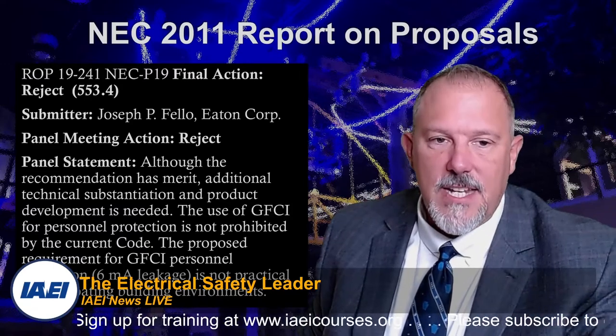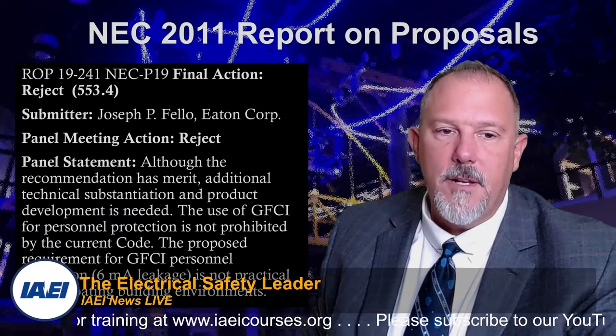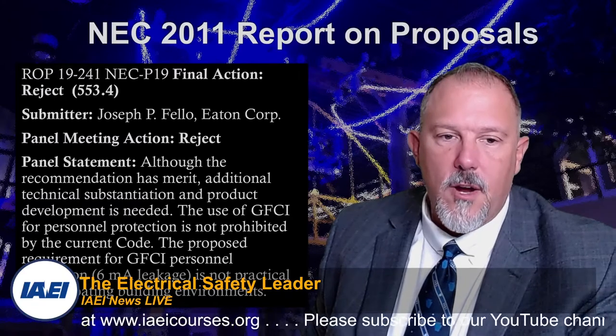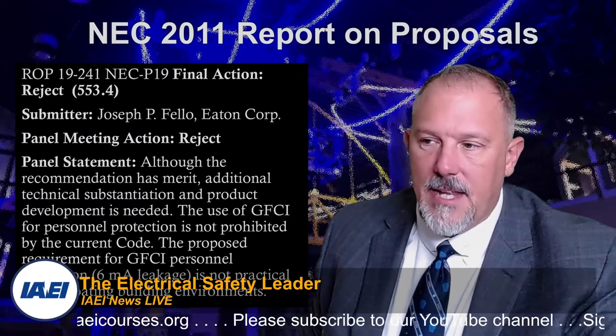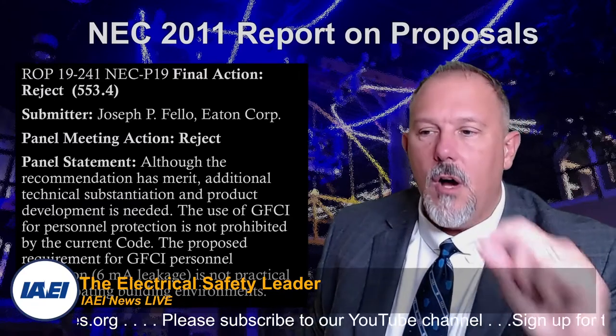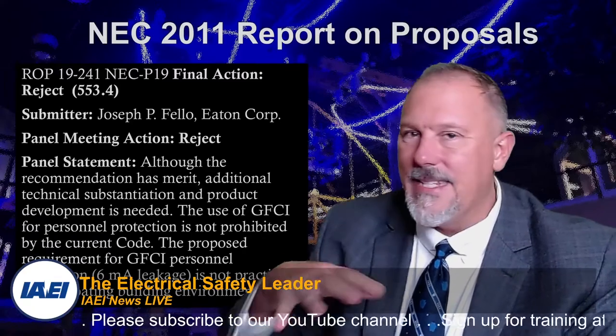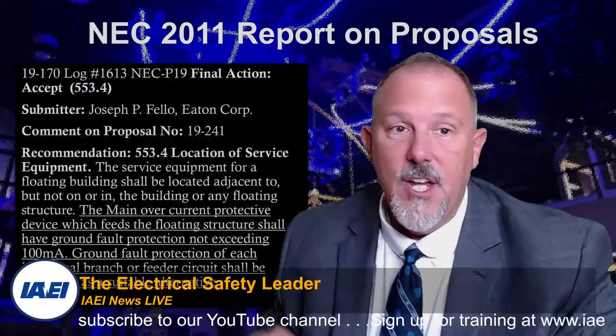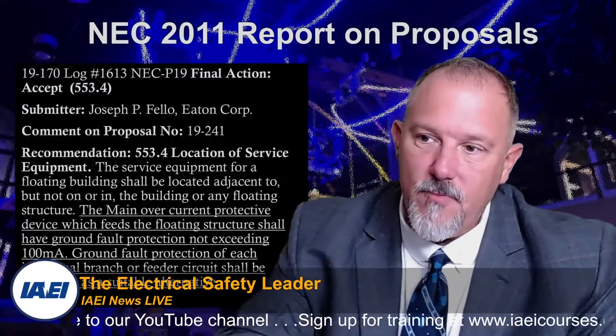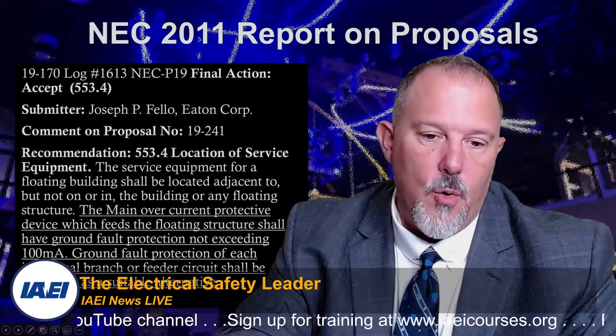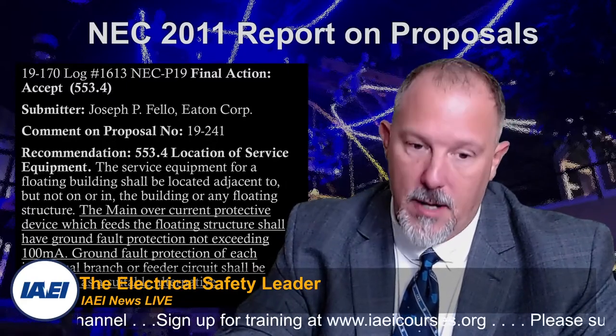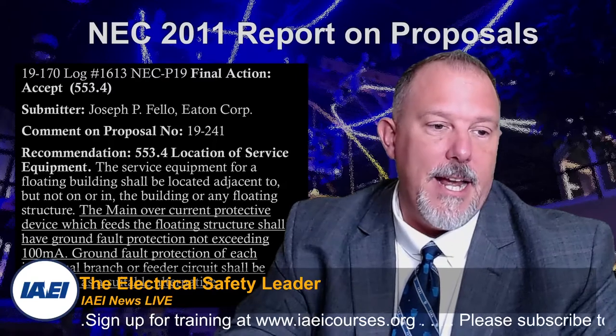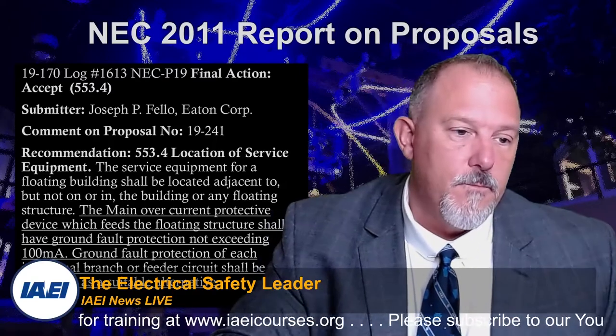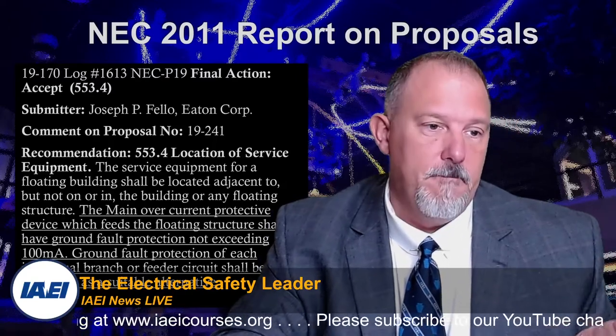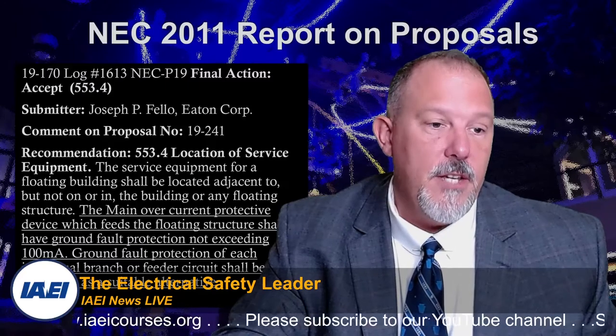The use of GFCI for personnel protection is not prohibited by the current code. The proposed requirement for 6 milliamp leakage is not practical for all floating building environments. And they said the same thing in 555. So what did we do? We came back with another proposal, or a public comment. And the public comment was what you see on the screen here.